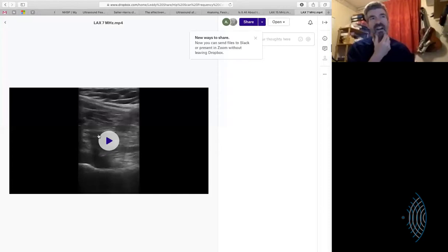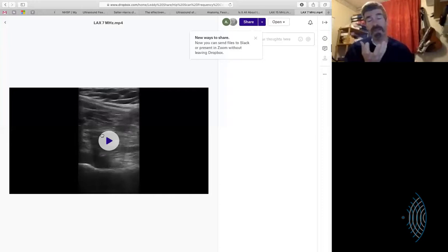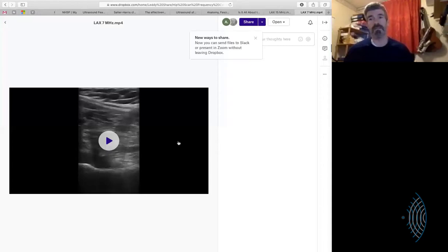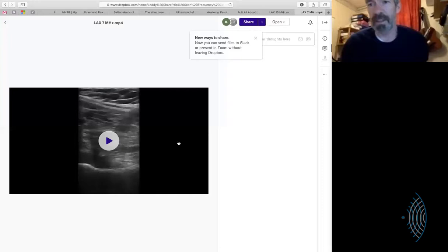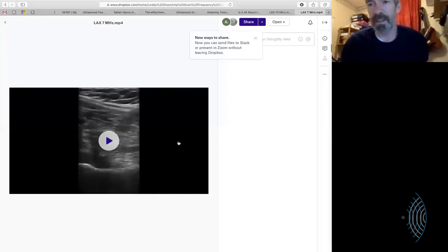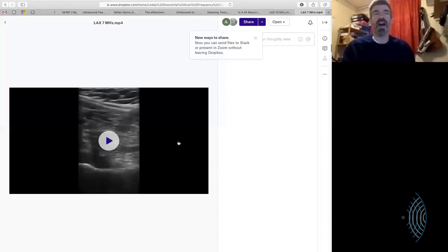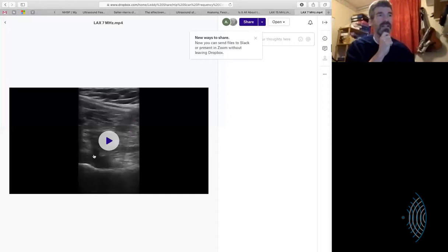Does it become more obvious at higher or lower frequency? It's just a good piece of kit. Back in the 2000s, compounding started to be developed — Philips particularly got a very good implementation; it's hardware and software, not all post-processing. Their machines were an order of magnitude better than everyone else's at the time. Sonosite got it as well, and everyone else developed it very quickly afterwards. All modern machines use quite a lot of compounding to varying degrees. What you're seeing there is issues with the software putting it together, giving you that degradation of the picture. So in theory your best part of the picture is in this area.